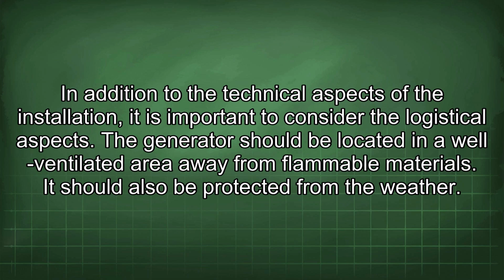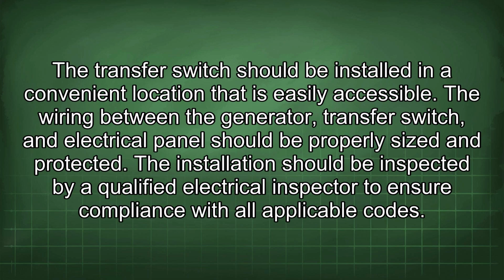It should also be protected from the weather. The transfer switch should be installed in a convenient location that is easily accessible. The wiring between the generator, transfer switch, and electrical panel should be properly sized and protected. The installation should be inspected by a qualified electrical inspector to ensure compliance with all applicable codes.